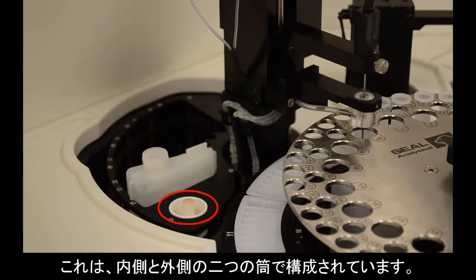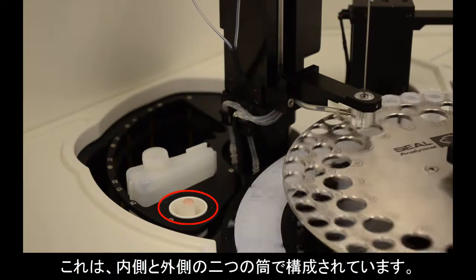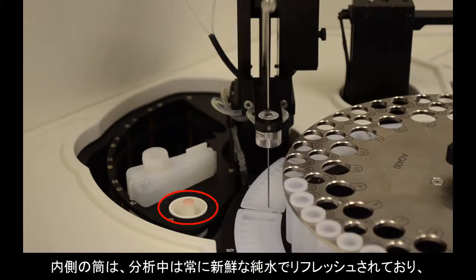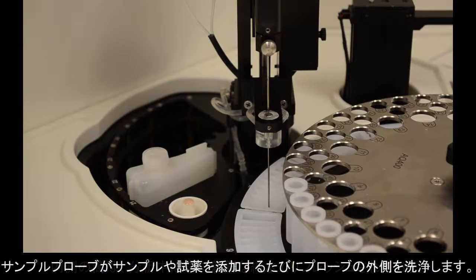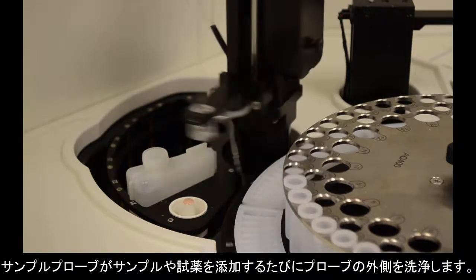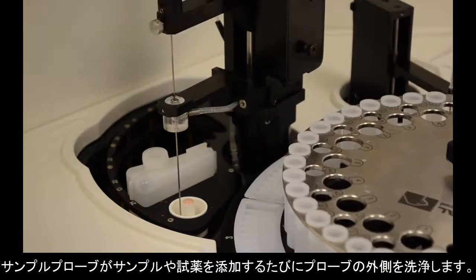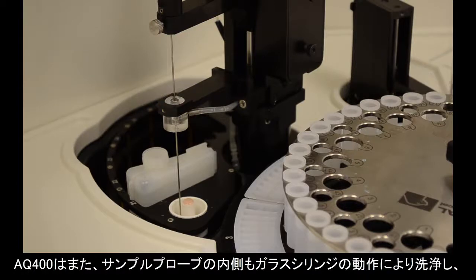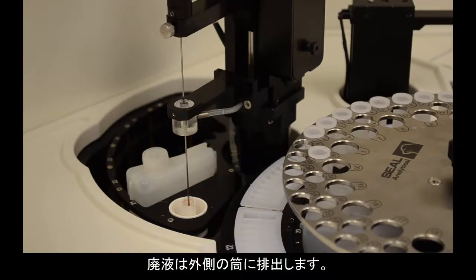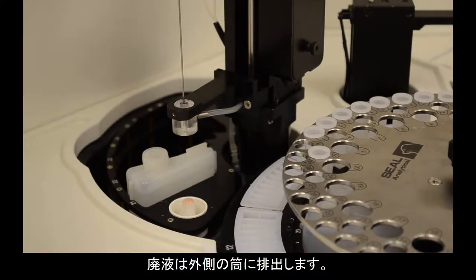The second location is the sampler wash station. This is comprised of 2 wells, an inner and an outer well. The inner well is refreshed with water throughout the run, and the probe will dip into this in between each sample or reagent addition, which cleans off the outer surface of the probe. The AQ400 also flushes clean water through the inside of the sample probe with the use of the syringe, which is then dispelled into the outer well to be drained away.